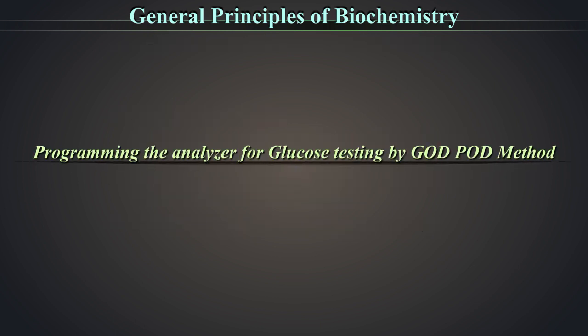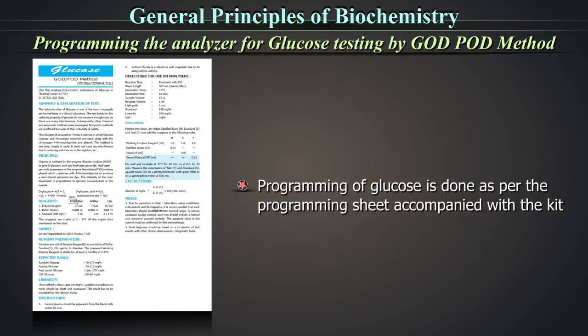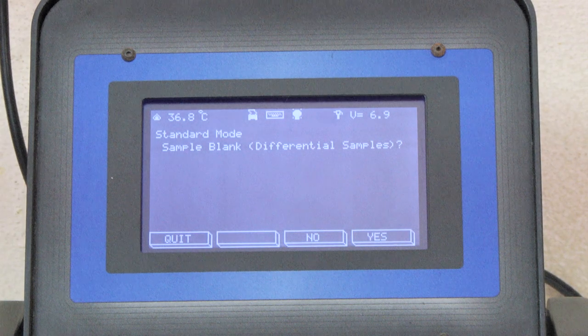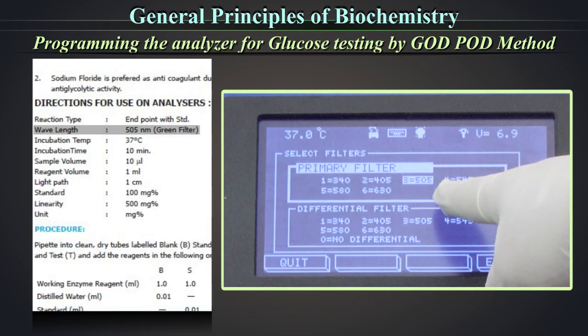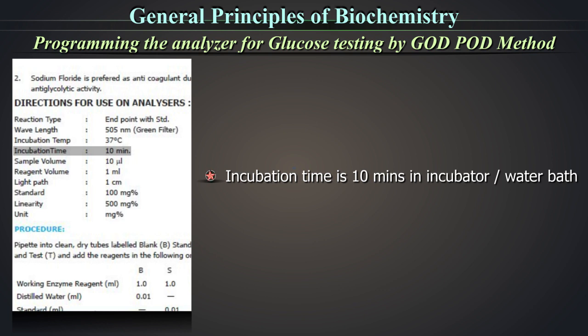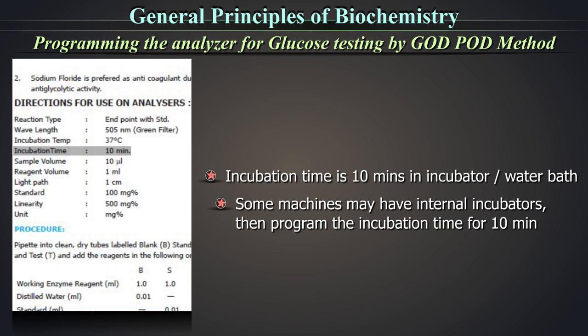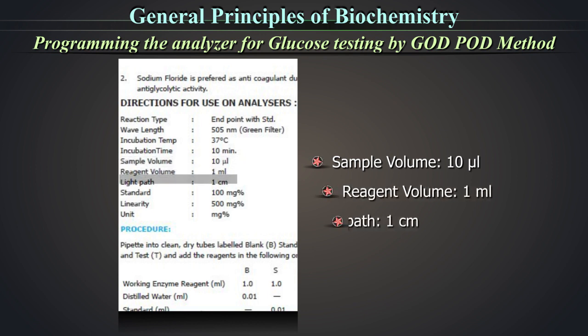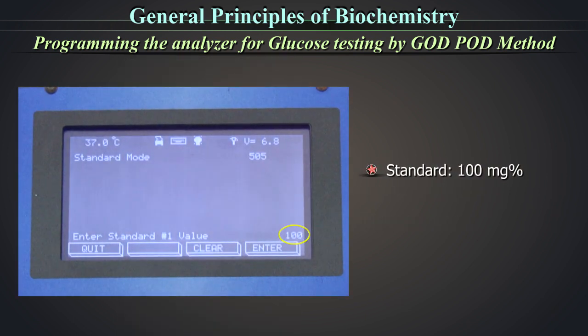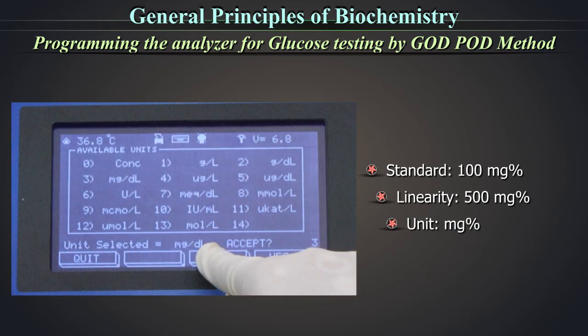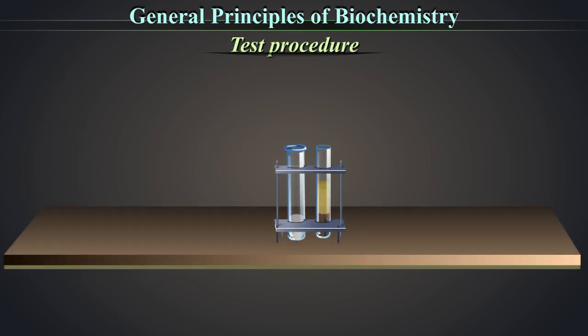Programming the analyzer for glucose testing: the programming of glucose is done as per the programming sheet accompanied with the kit. In this machine, go to the display screen and key in the following. From the mode menu, select single standard mode which is endpoint reaction. Select primary filter at wavelength 505 nm — green filter. Incubation temperature: 37 degrees Celsius. Incubation time is 10 minutes in incubator or water bath. Some machines may have internal incubators; then program the incubation time for 10 minutes. Sample volume: 10 microliters. Reagent volume: 1 ml. Light path: 1 cm. For the standard, feed the value specified on the kit insert — here it is 100 mg percentage. Linearity: 500 mg percentage. Unit: mg percentage. As blank, reagent and standard have already been run to get the calibration factor and the QC has been verified, we are now to run the test sample.